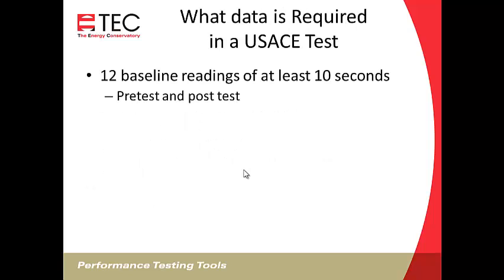So the U.S. Army Corps test requires you to have 12 baseline readings of at least 10 seconds each, and the reason I'm going over this is because it's important you know what data needs to be included in the test, because TECLOG3 is not a fully automated test.